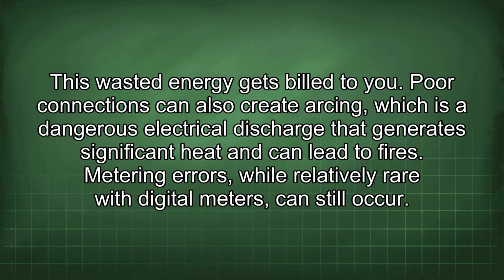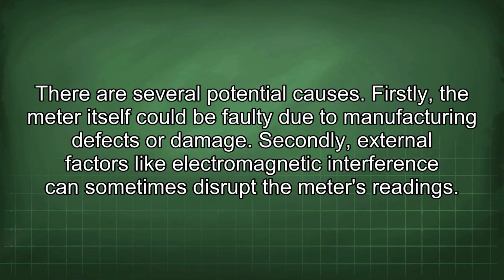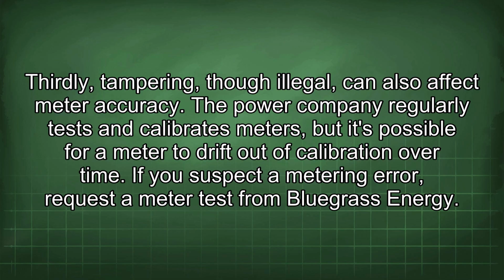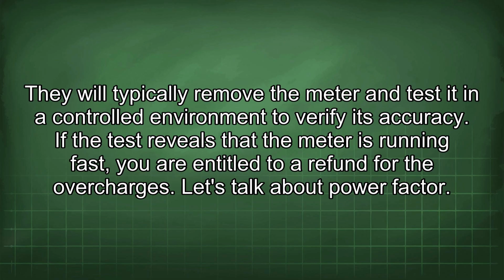Metering errors, while relatively rare with digital meters, can still occur. There are several potential causes. Firstly, the meter itself could be faulty due to manufacturing defects or damage. Secondly, external factors like electromagnetic interference can sometimes disrupt the meter's readings. Thirdly, tampering, though illegal, can also affect meter accuracy. The power company regularly tests and calibrates meters, but it's possible for a meter to drift out of calibration over time. If you suspect a metering error, request a meter test from Bluegrass Energy. They will typically remove the meter and test it in a controlled environment to verify its accuracy. If the test reveals that the meter is running fast, you are entitled to a refund for the overcharges.